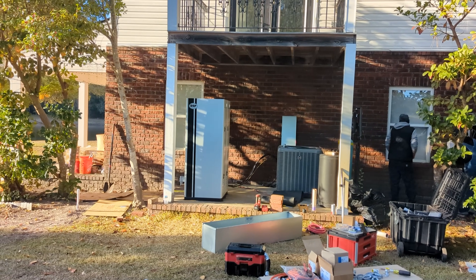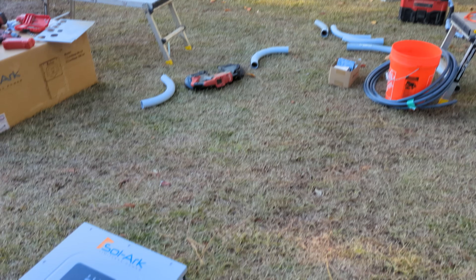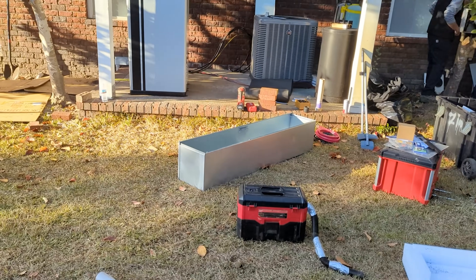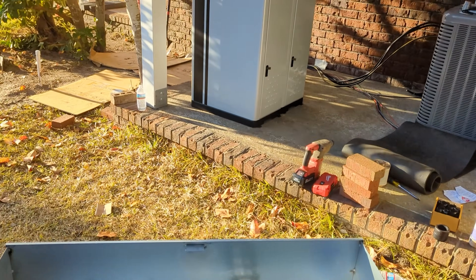We're back the next week with the ground mount done, now building out the electrical. This is a new one for me - my first outdoor install. When you go outdoor or damp location, you've got to have NEMA 3R equipment: outdoor-rated gutters, outdoor Myers hubs. You spend a lot more money on electrical parts to do all this outdoor work than you would if it were in a mechanical room.